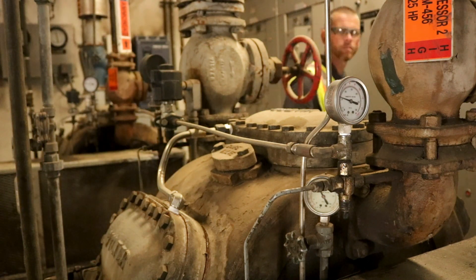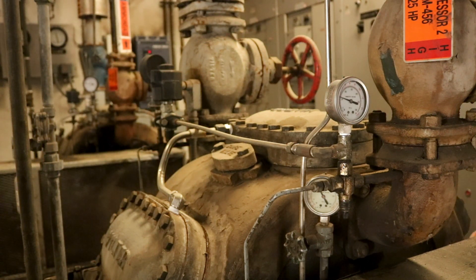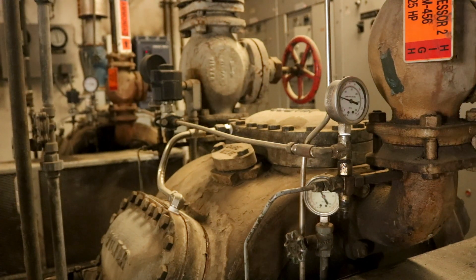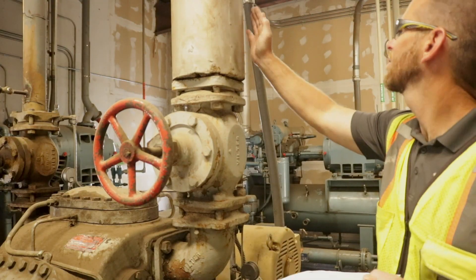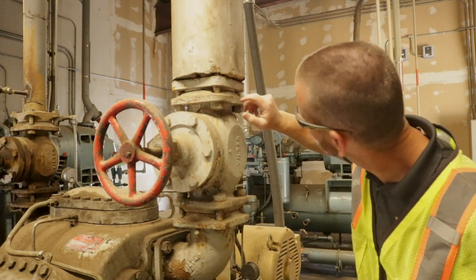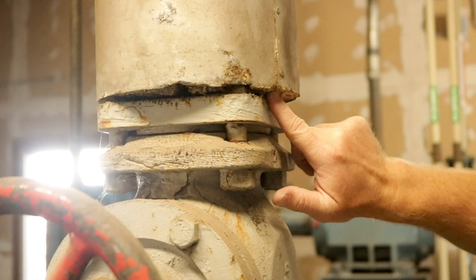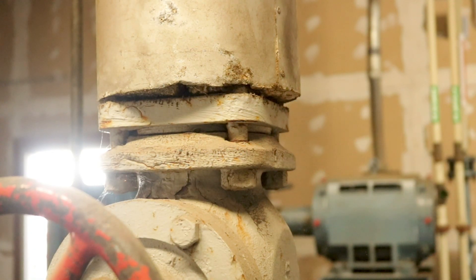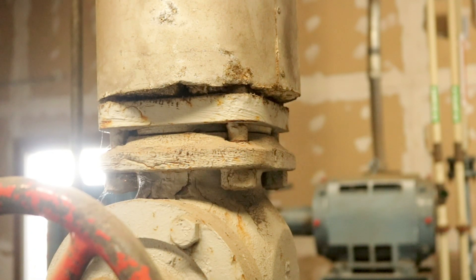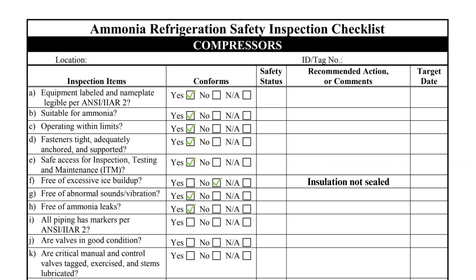Frost or ice buildup on the crankcase or oil separator would indicate a failed oil heater and must be addressed. A compressor in this condition must be locked out until necessary repairs can be made. This suction pipe insulation is not properly sealed, so a deficiency should be noted.